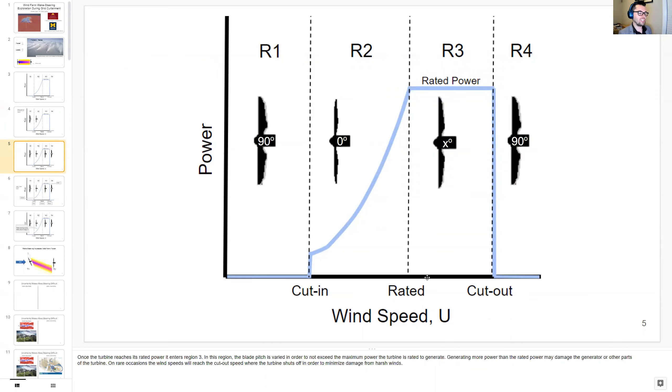Once the turbine reaches its rated speed, it enters region 3. In this region, the blade pitch is varied in order to not exceed the maximum power the turbine is rated to generate. Generating more power than rated power may damage the generator or other parts of the turbine.